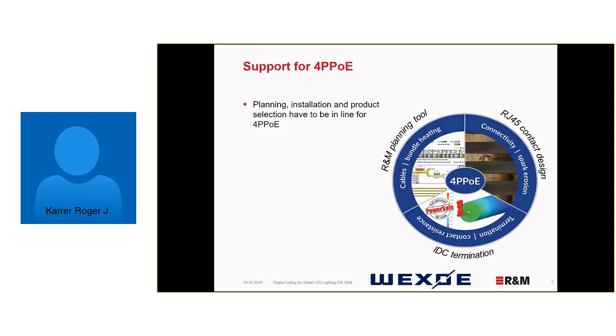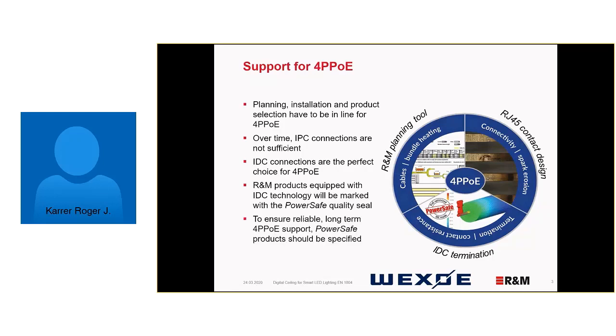When looking at this, it's important to consider all these aspects. The planner can take care of planning, but the rest must be handled by the manufacturer. We believe IPC connections are not sufficient over time because inner resistance will increase. The IDC is the perfect choice for four-pair PoE because it is consistent in its resistance — it will not alter and will therefore stabilize your connection.